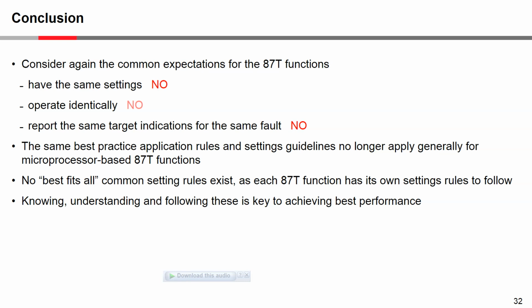If that fault stays on just a little bit longer than necessary, you could face a lot of other things like tank rupture. You could face ignition of the oil. You could face a number of other things that would be quite significant, rather than just a transformer that is now faulted and needs repair. I've actually seen a substation where the transformer caught fire. It burned for like 3 days, and the rest of the substation was twisted metal. So, yes, you would want to get rid of that fault as soon as possible. And I would say for transmission level transformers, it definitely makes sense to put a system A and a system B. Whether system A and system B have to be different, that's a different philosophical discussion. But the fact that you have two equal operating systems, A and B, if I was working in a utility, I would do that.